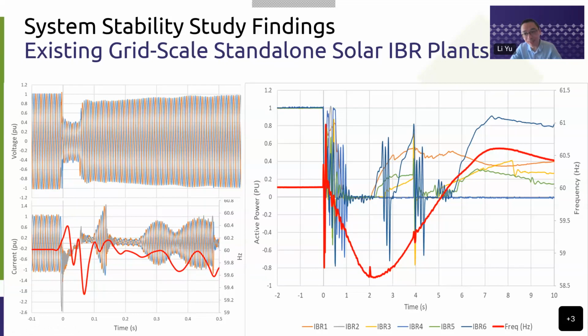Using slow speed recording data, we can look into all 6 plants' performance during this event. From 0 seconds when the fault happened to 1 second, none of them shows any support to the system during the frequency event. At around 1 second, system frequency had already dropped to around 59.4 hertz, very close to the point where the frequency event is going to trip system DER. After 1 second, most of the IBR plants went to very minimum active power output, and the frequency continued to drop. The nadir reached 58.7 hertz, and a lot of legacy DER got tripped.